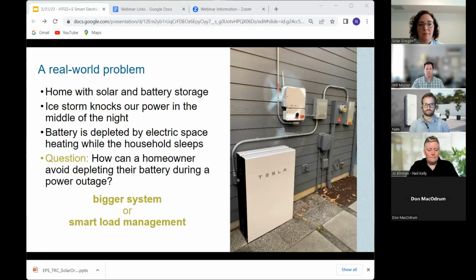The more practical solution would be a system in place that shut out the heating system from the battery, at least until the occupants had a chance to wake up and assess the situation. A protected loads panel could have helped, though they would need to turn to space heaters because the heat pump wouldn't have been on that protected loads panel. But smart load controls could have allowed the occupants to preset the heat pump as a non-essential load. That way they could have woken up to a slightly cooler house with a full, or at least more full, battery, to strategically navigate the power outage.